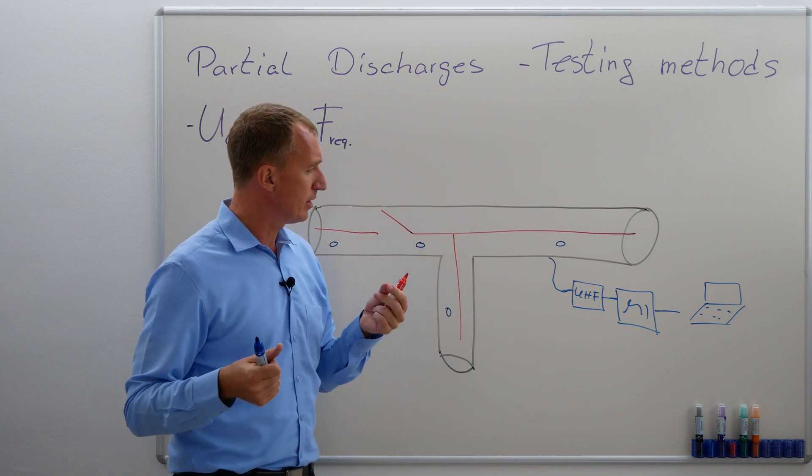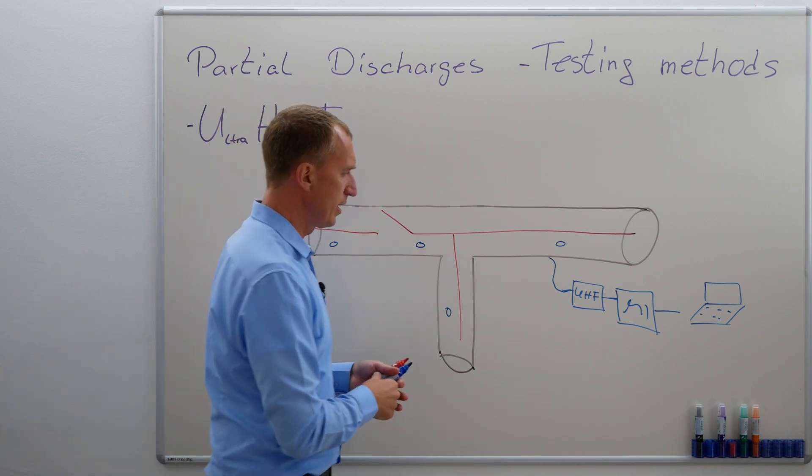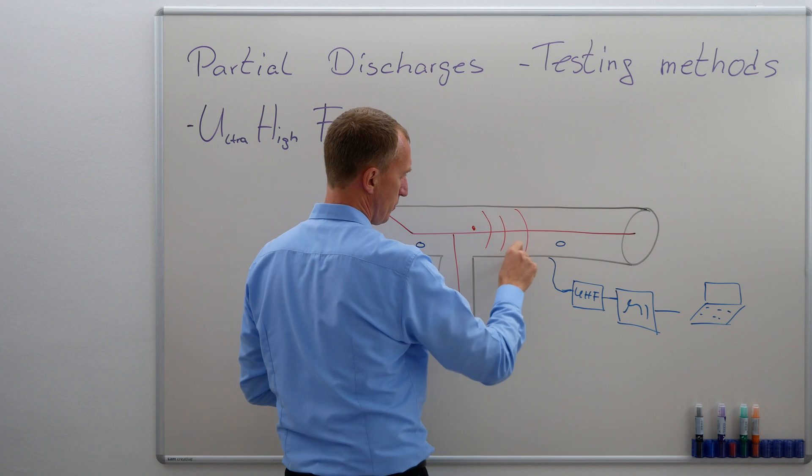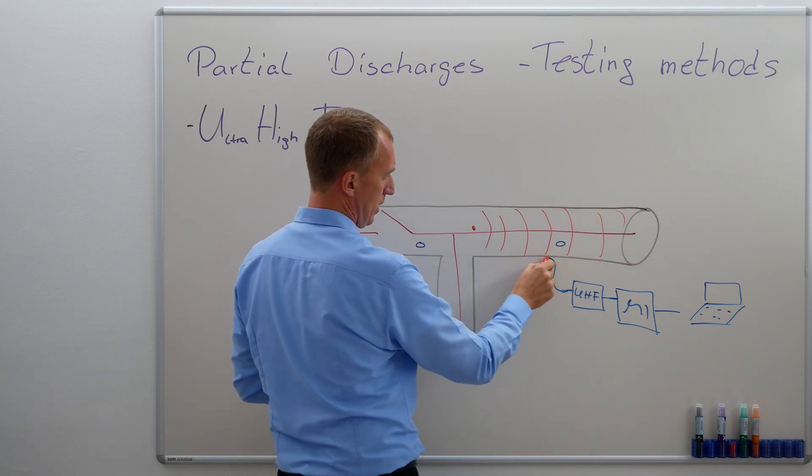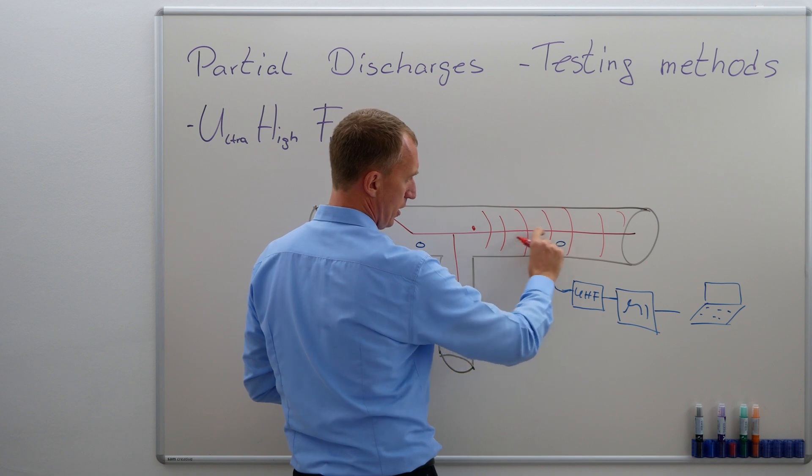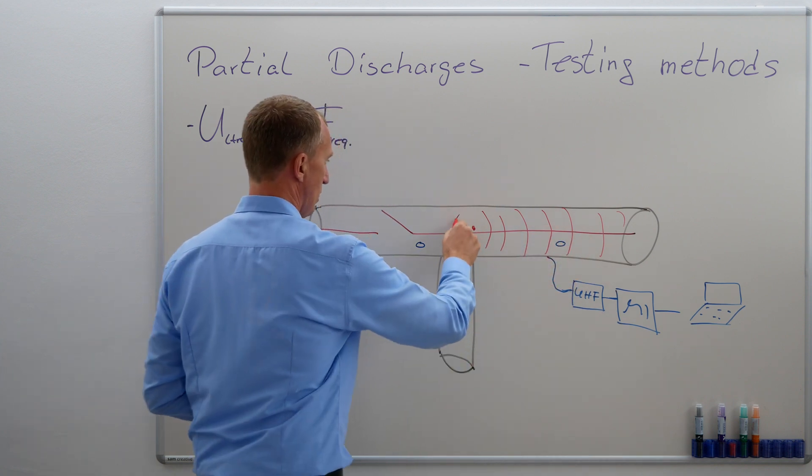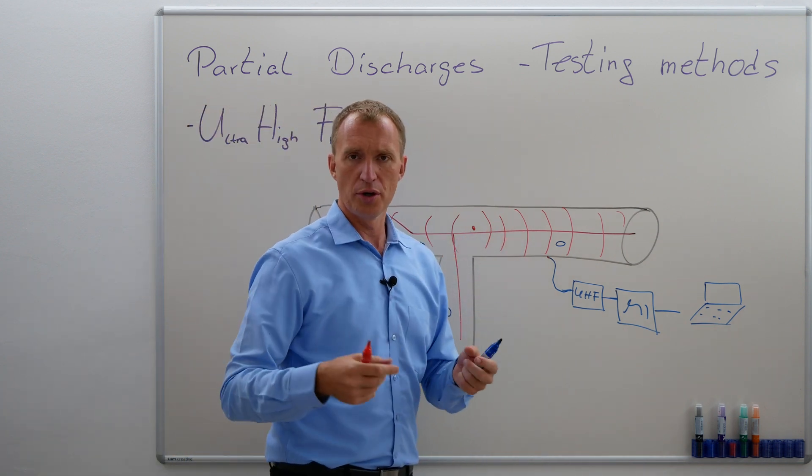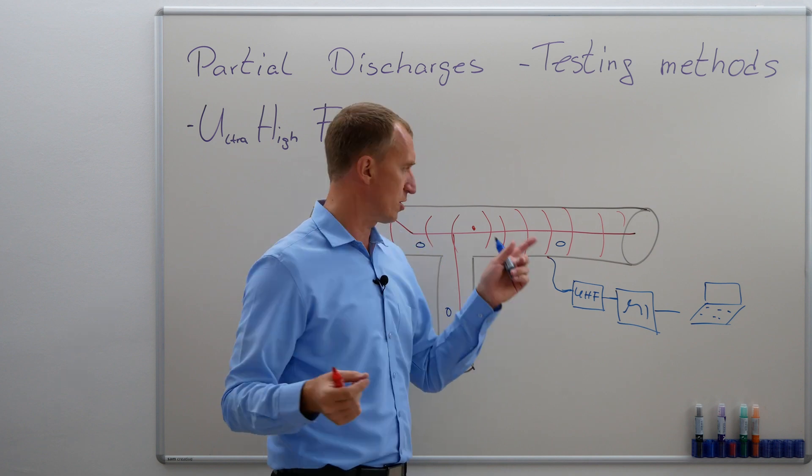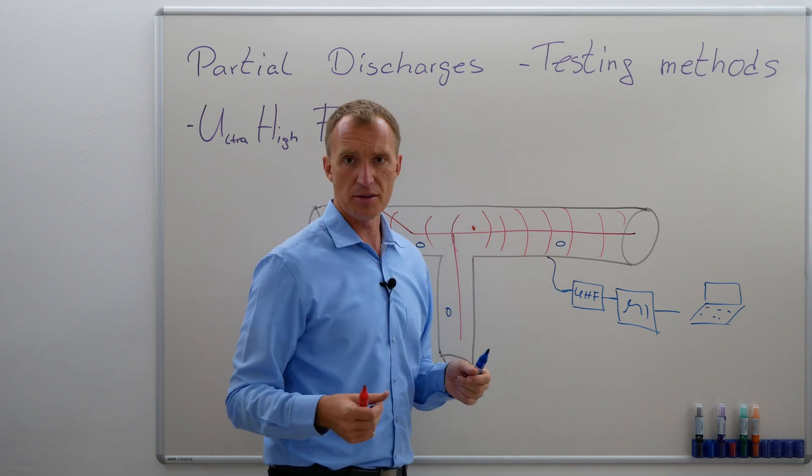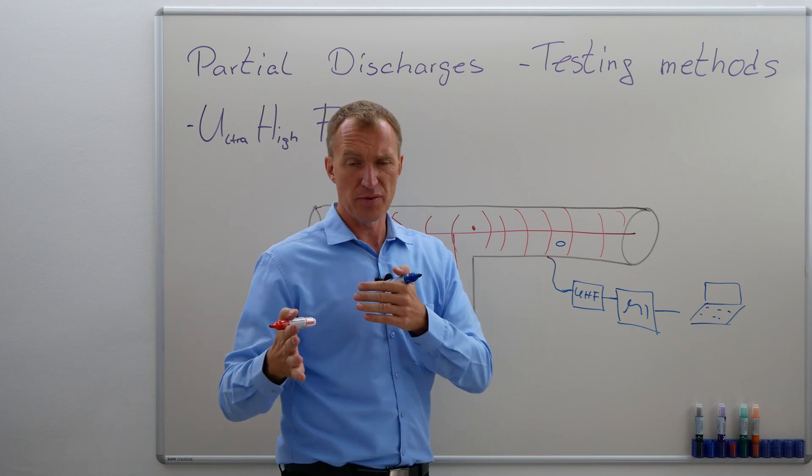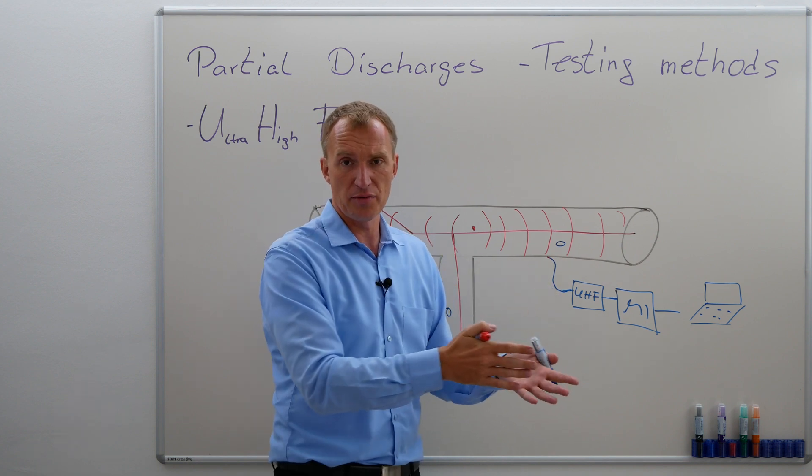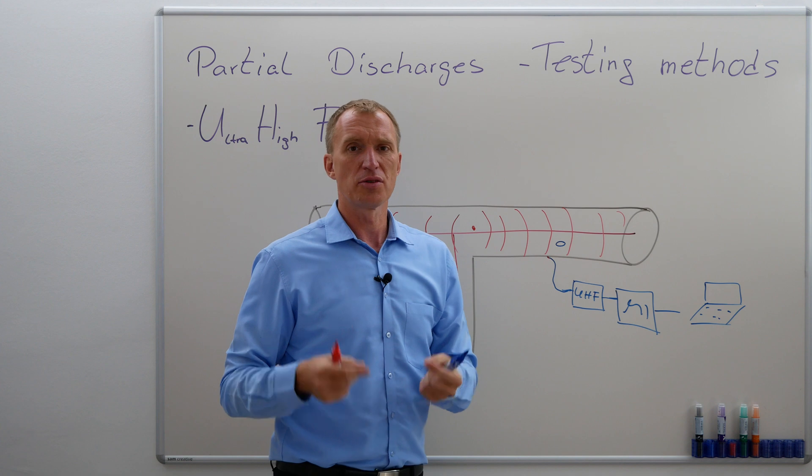Once again, you can't really calibrate, because once again, if you have a partial discharge inside here, the wave will travel inside here, right? And when it hits my UHF sensor, or it travels on here, I would be able to sense it, it will travel in here as well. Calibration would only be possible once I know where it is, and I know the distance between the source and my sensor. And then the next thing is, depending on the frequency band I'm measuring in, it changes. So this is not so easy.